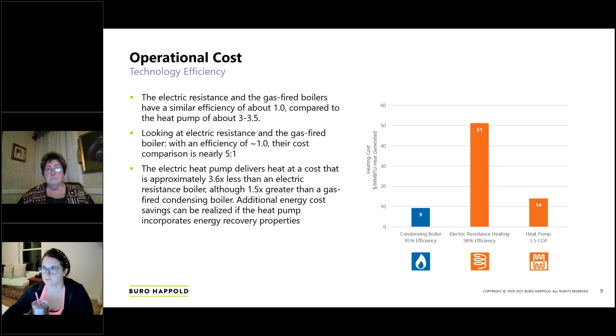The heat pump chiller is also fairly efficient in that it's able to have some integral heat recovery properties. So specifically in the simultaneous heating and cooling mode, such as when the building would be in the shoulder season, the efficiency of the unit does increase exceptionally to about a COP of 6, which is very high performance heating capabilities or heating efficiencies.